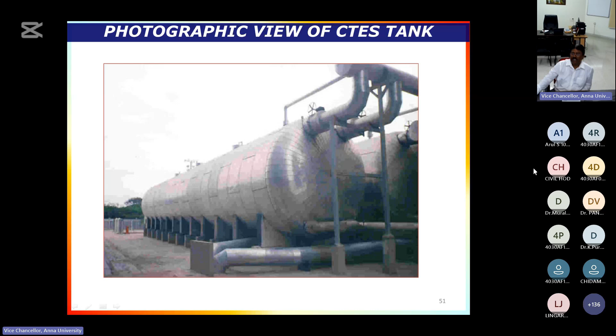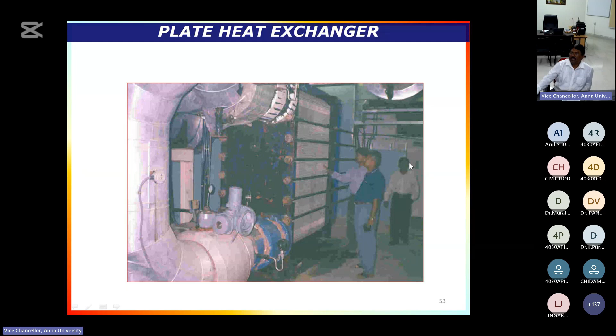This is the plate heat exchanger, which decides how much energy is sent to the air handling unit. Cool water from the storage tank comes to this plate heat exchanger, which transfers energy to the chilled water. The chilled water is then taken to the air handling unit, with the plate heat exchanger deciding the load based on demand.